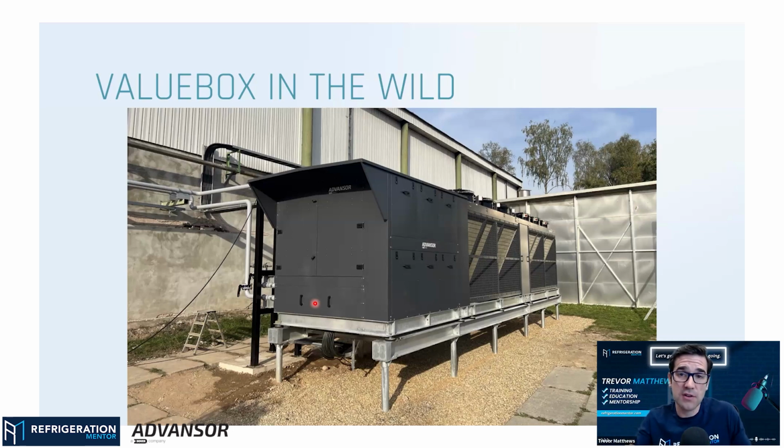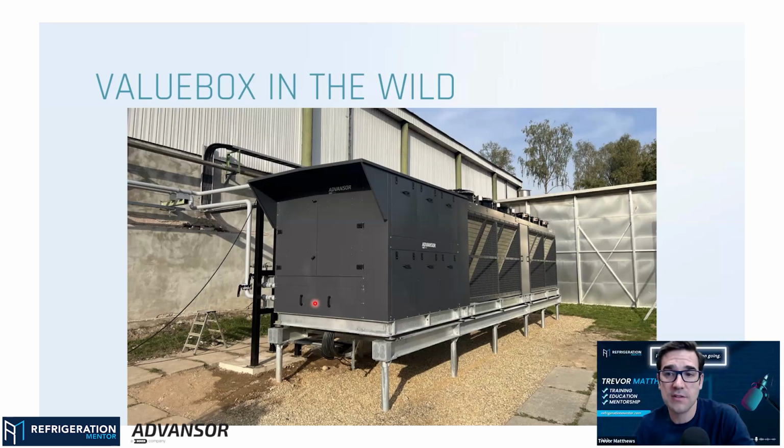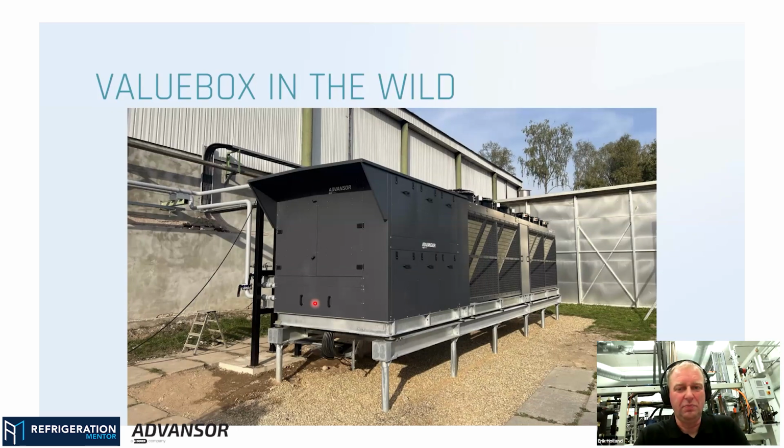You have to go back and pull a vacuum on that receiver or that oil reservoir. So this actually can save time, and it's not that difficult to do. I really like to do it just for some extra security for myself. Then I isolate the oil vessel, so I close all the valves in and out and connect the vacuum pump directly on the vessel.